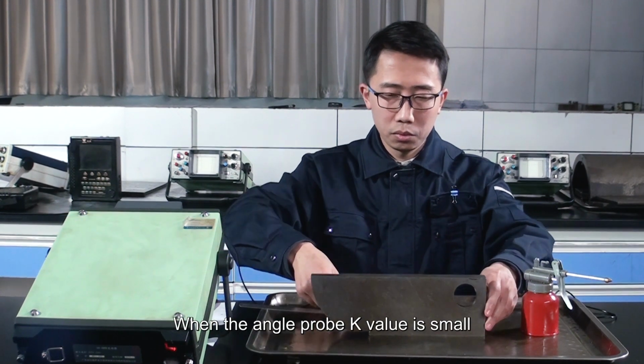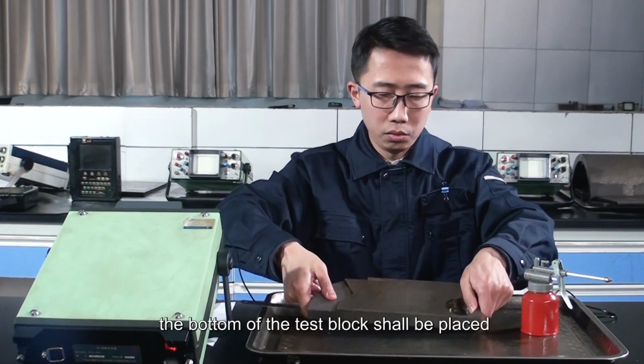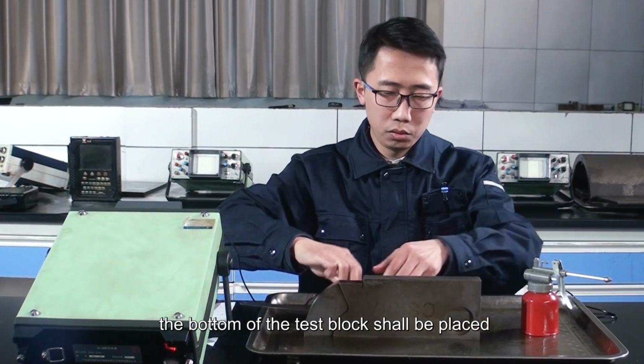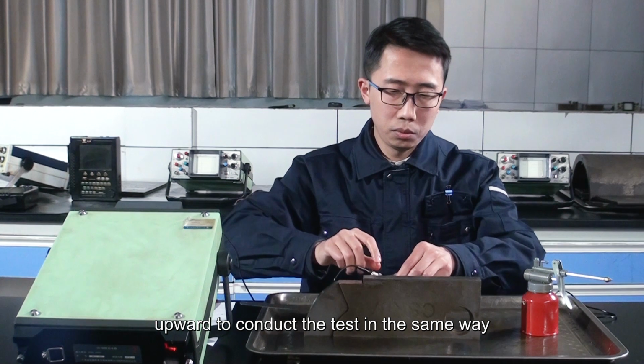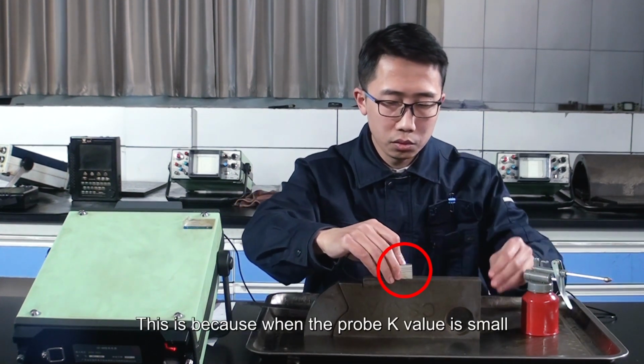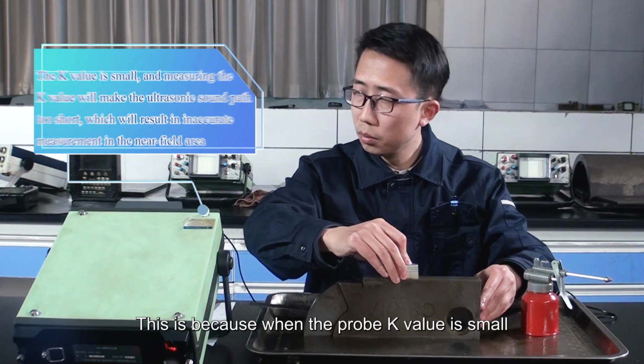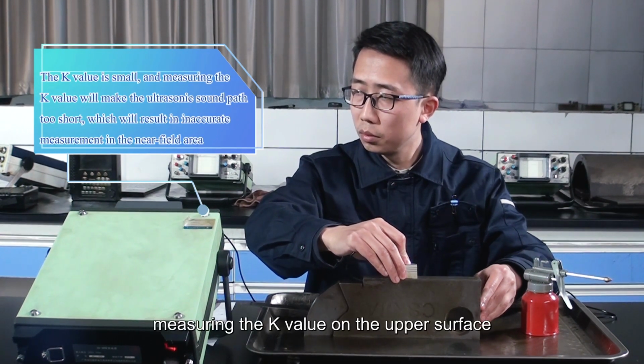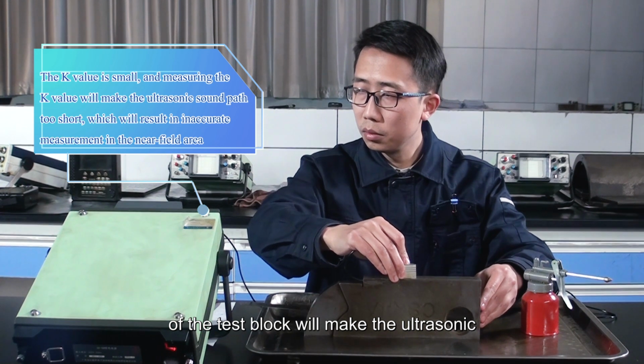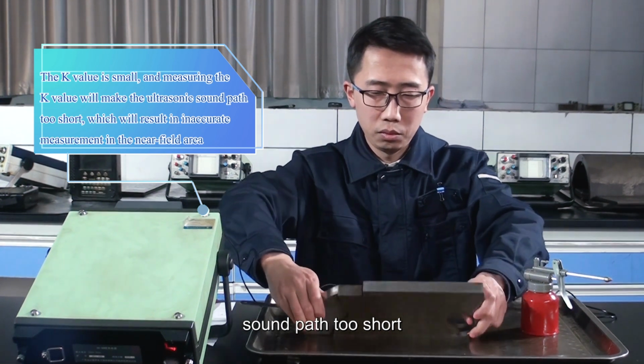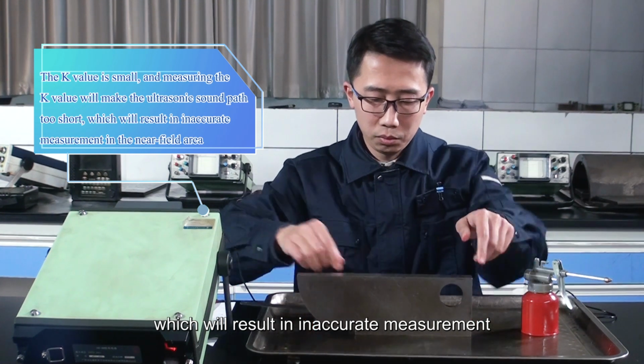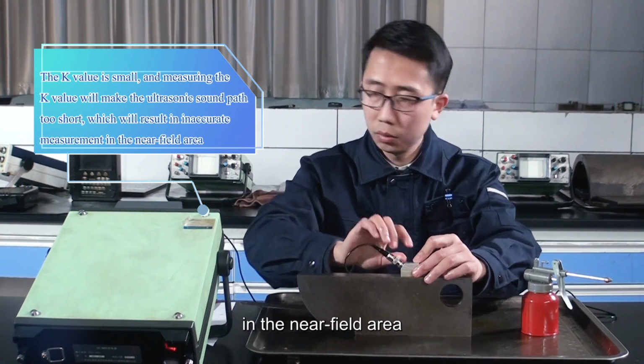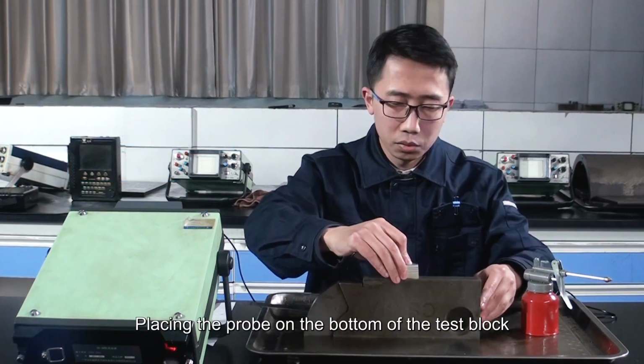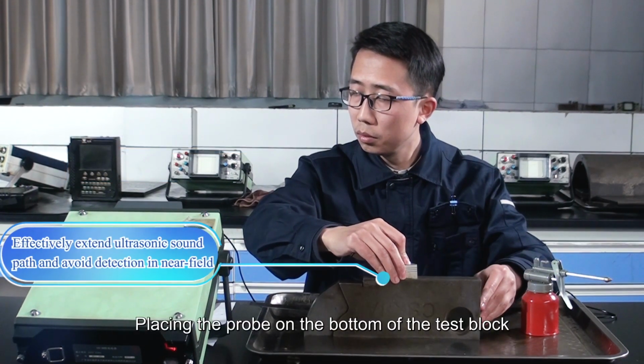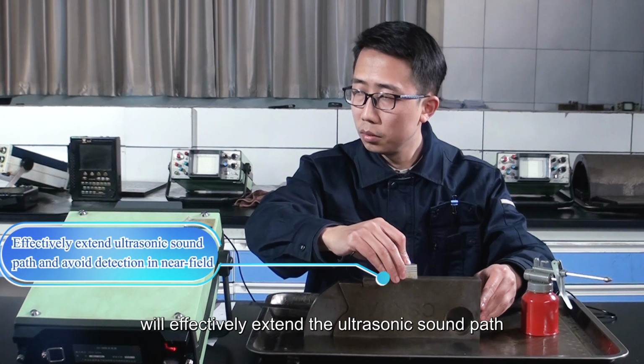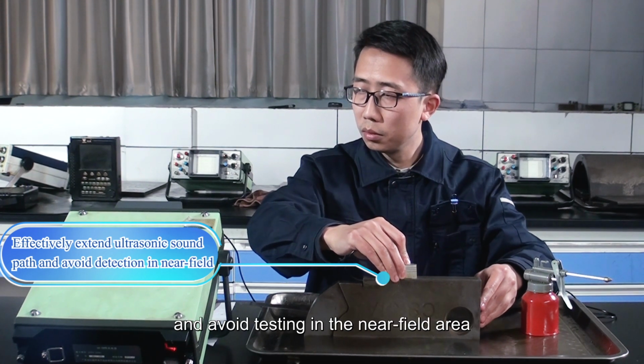When the angle probe K value is small, the test block should be placed with its bottom side upward to conduct the test in the same way. This is because when the probe K value is small, measuring on the upper surface of the test block will make the ultrasonic sound path too short, which will result in inaccurate measurement in the near-field area.